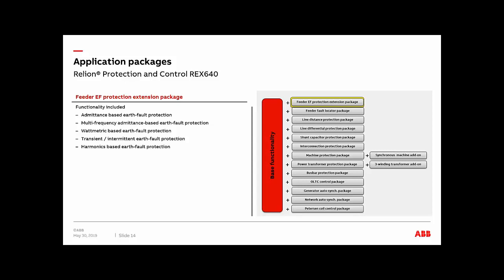When it comes to multi-frequency admittance-based ground faults, this is mainly for distributed compensation, and it provides enhanced ground protection performance in feeders with distributed compensation. This is specifically for feeders that have distributed compensation, and it can be applied regardless of the location of the distributed coils that are used for the compensation. So this is a little bit more specific. The wattmetric-based function is a directional method for detecting ground faults in compensated networks with radial topology. This is the thing to keep in mind here. This one specifically is for networks with radial topology, and we do not recommend using it in mesh systems.